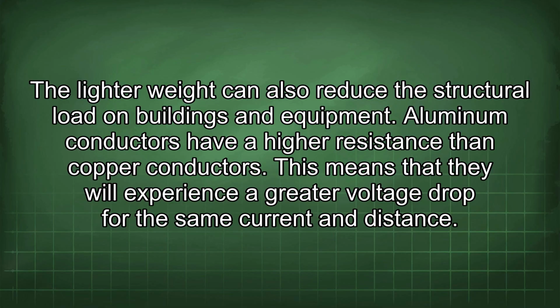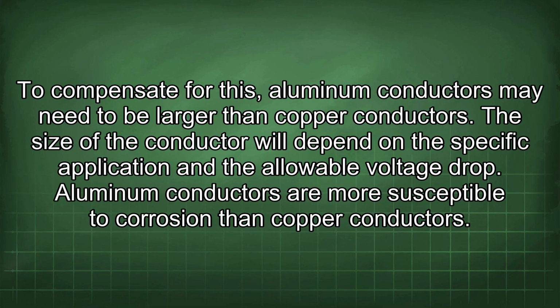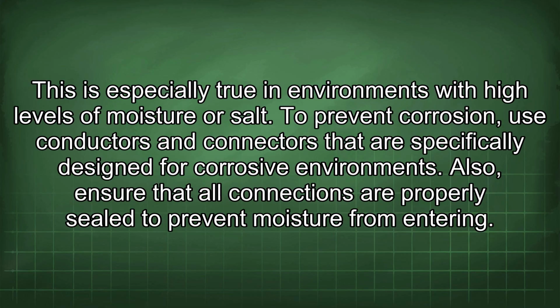Aluminum conductors have a higher resistance than copper conductors. This means that they will experience a greater voltage drop for the same current and distance. To compensate for this, aluminum conductors may need to be larger than copper conductors. The size of the conductor will depend on the specific application and the allowable voltage drop. Aluminum conductors are more susceptible to corrosion than copper conductors. This is especially true in environments with high levels of moisture or salt. To prevent corrosion, use conductors and connectors that are specifically designed for corrosive environments. Also, ensure that all connections are properly sealed to prevent moisture from entering.